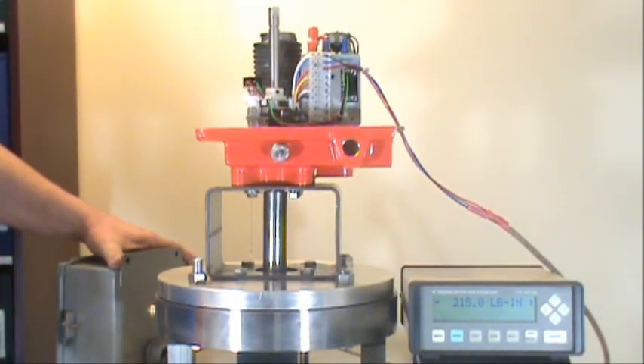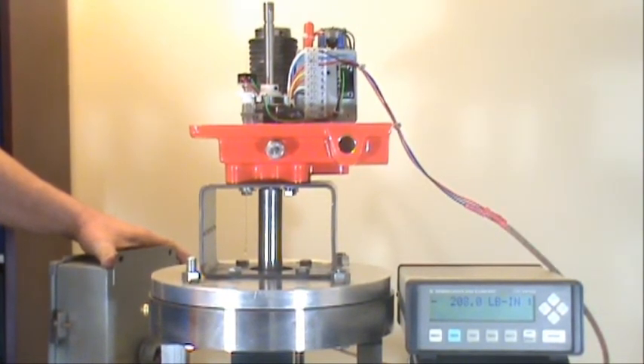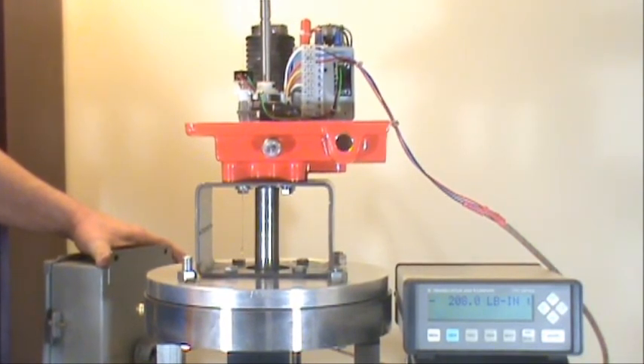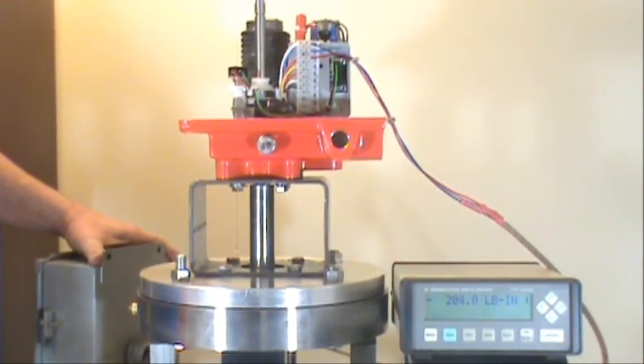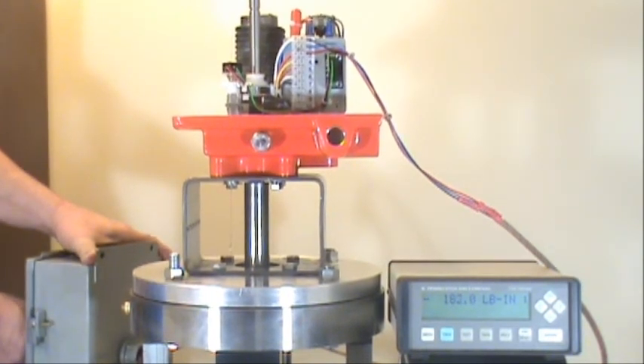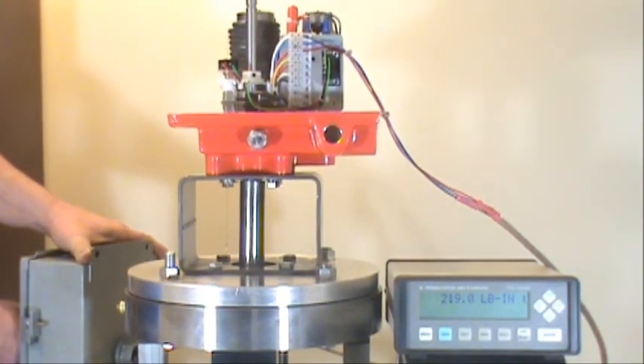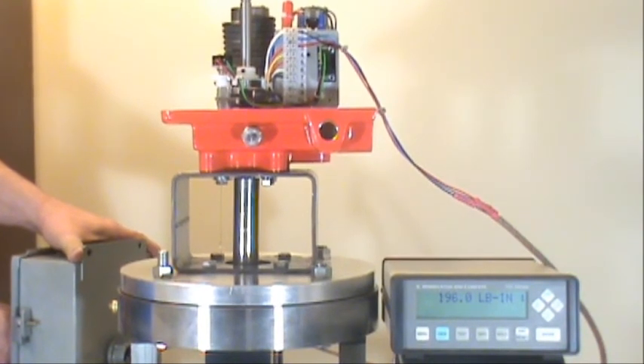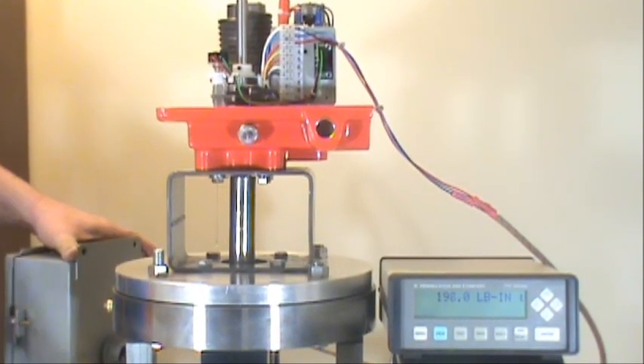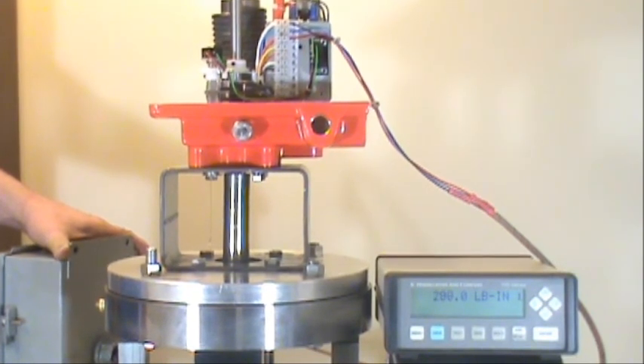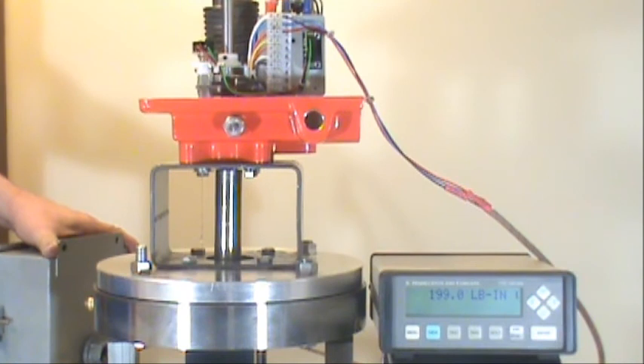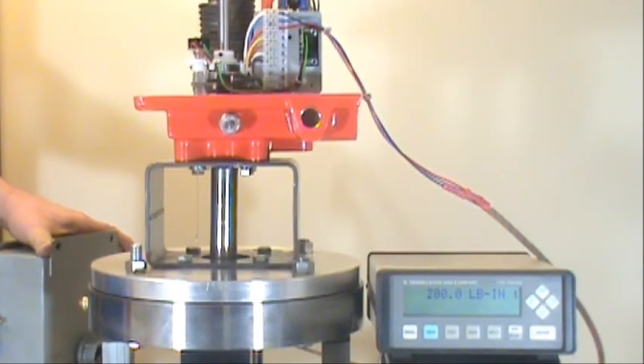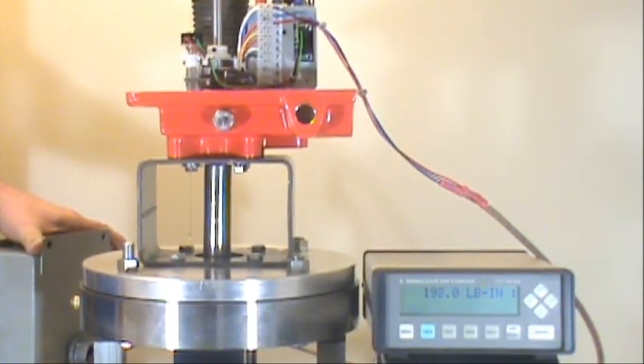Running it to the open position so we can go ahead and fail it. Lost the power. Good. Okay. About 220 inch-pounds was the highest spring close. Yeah, but even at the end of the spring's tension, it was still over 200 or right at 200 inch-pounds.